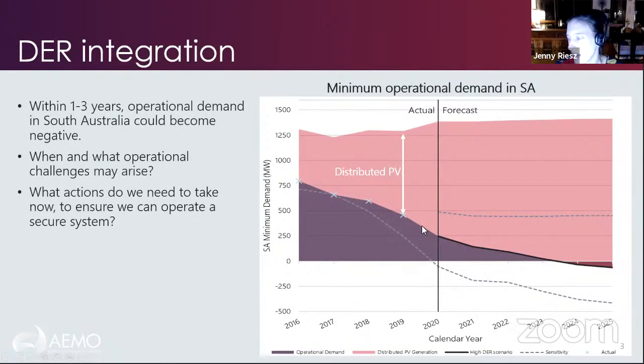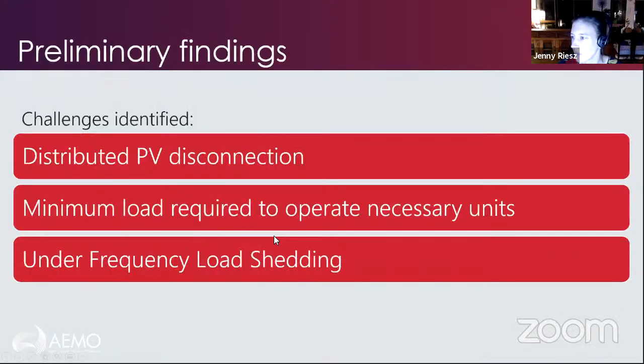We anticipate in the next year or two that we're going to hit periods of time where that part of the grid will be entirely supplied by rooftop photovoltaic systems. And it's only weakly interconnected to the rest of the grid. It can actually island from the rest of the grid at some times. So we're doing the work to understand how do we actually operate a grid that runs with 100% of the power very soon coming from rooftop photovoltaic systems, and looking at what we as the system operator have to do to be able to run that grid successfully.